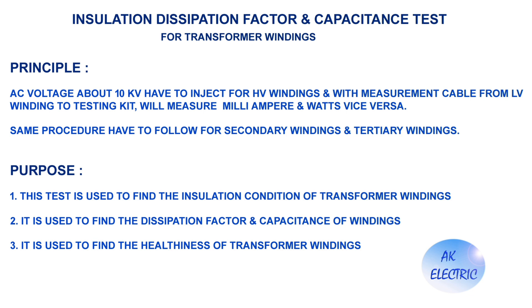First we'll see the principle of the test. AC voltage of about 10 kV is injected for HV windings, and with a measurement cable from LV winding to the testing kit, we measure milliampere and watts. The same procedure is followed for secondary windings and tertiary windings.